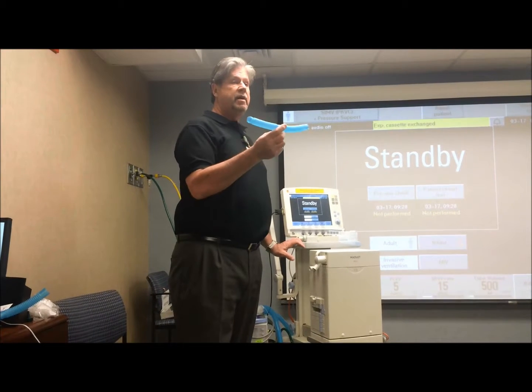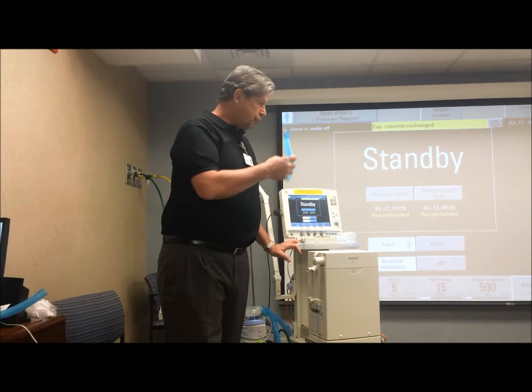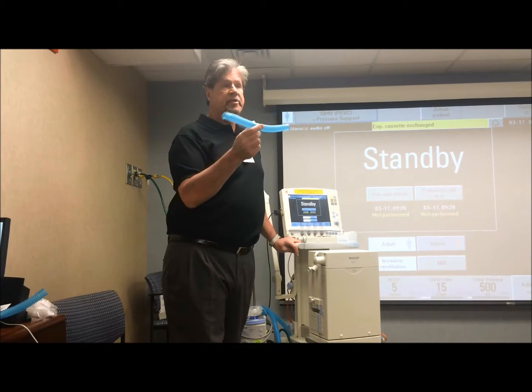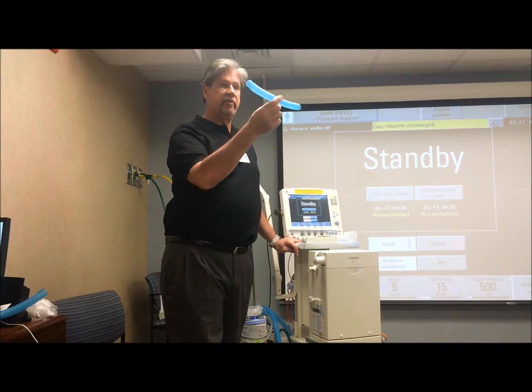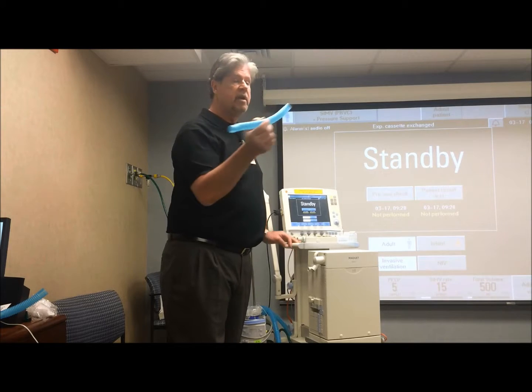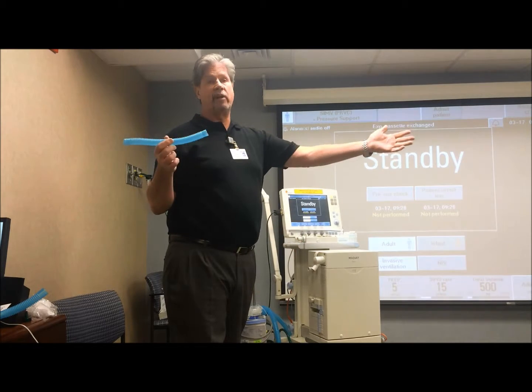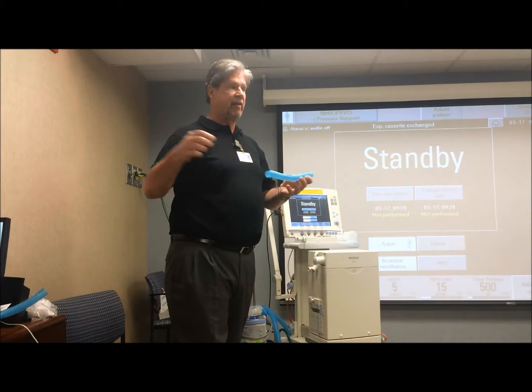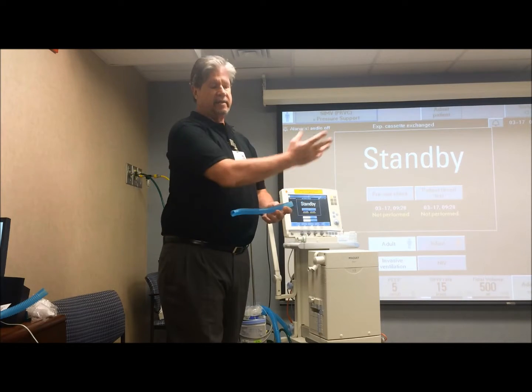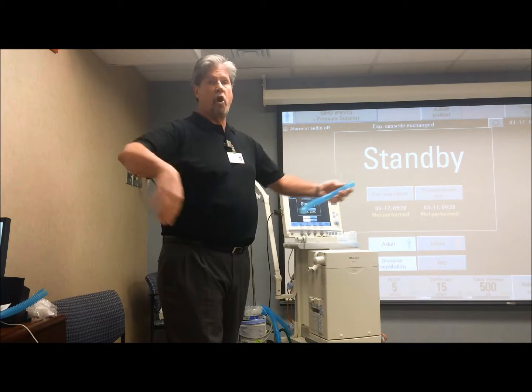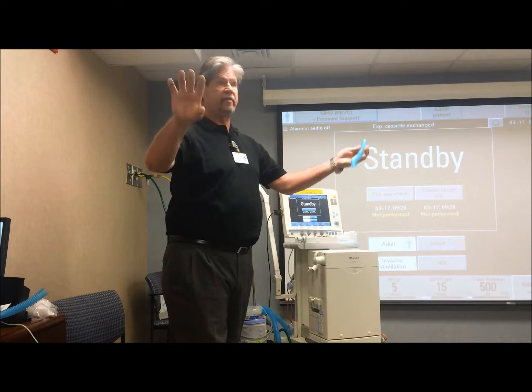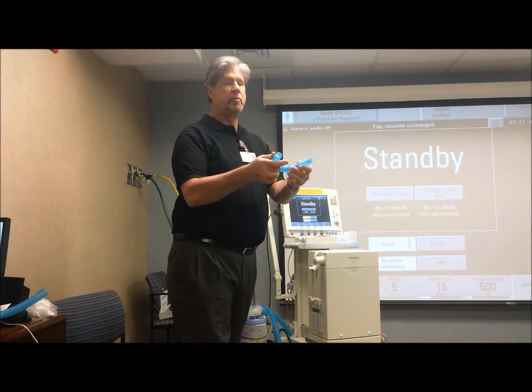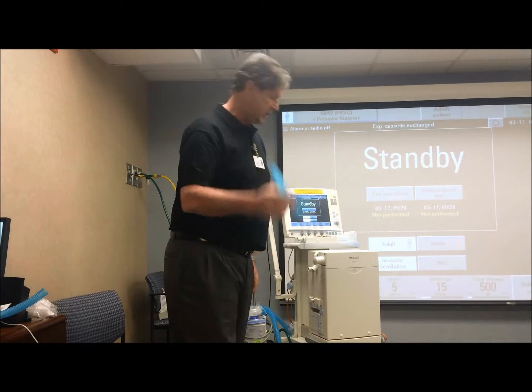Test lung, right? And the test tube is probably long gone in some of these machines, so you can use a piece of tubing that's about this long. For an aerosol, you can't use anything longer because it'll fail, because the ventilator will think that it's pushing too much flow through the longer circuit, and it'll think that there's a leak somewhere. So you need a small one about the length of 2 aerosol pieces.